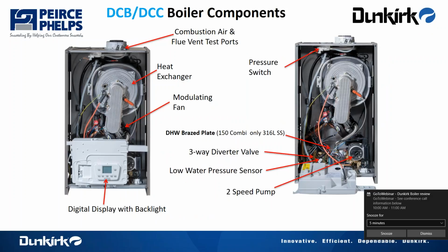It shows the boiler with the front jacket panel off. A really nice jacket system that we manufacture in Dunkirk. Insulated, tested for infiltration, so that we have very little inside air that permeates through the jacket closure. That's a test standard that we had to abide by. The heat exchanger, as we said, a flat tube stainless steel heat exchanger. The modulating fan, the display with the display tray in the up position. The combustion air ports, we can test both incoming fresh air, and then we can also test outgoing combustion air should we need to verify the readings that the module is giving us.